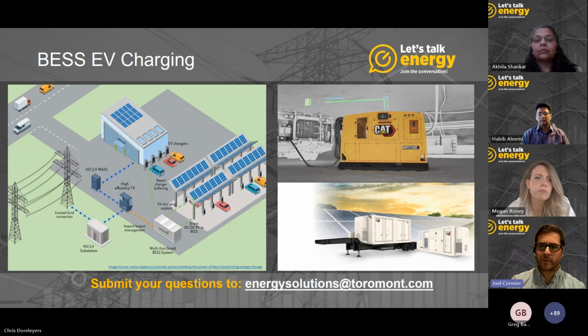Yeah, sure. So, one application that we may see having the use of a battery energy storage system would be having that battery energy storage system installed at a dock or a wharf. So we are starting to see electrification in commercial vessels. However, the utility infrastructure and the available utility power at these locations may not be significant enough to charge the electrified vessels in a reasonable amount of time. So by adding a battery energy storage system at the docks, we can actually slowly charge the batteries using the capacity that the utility does have available, and then discharge the stored energy in the battery energy storage system for charging those vessels. This solution would allow for fast charging of those vessels.